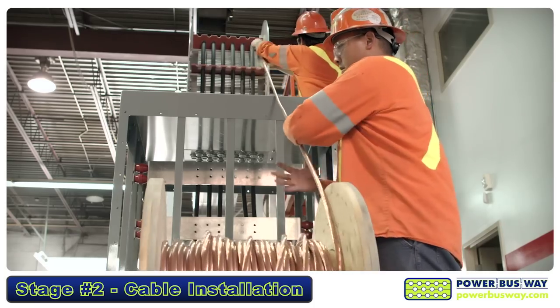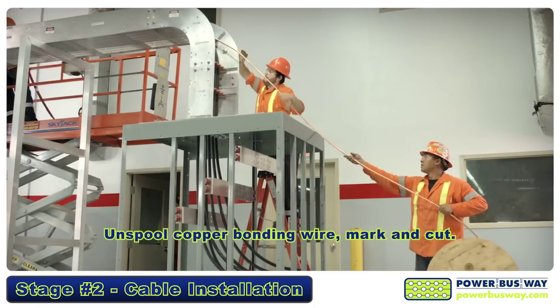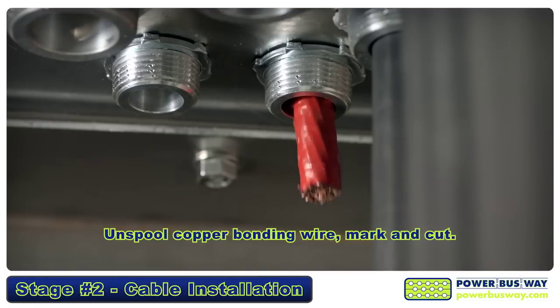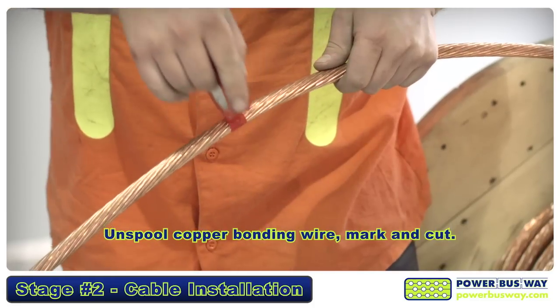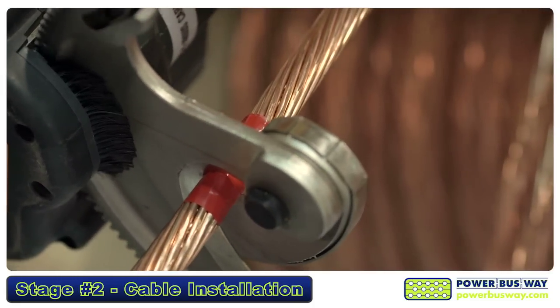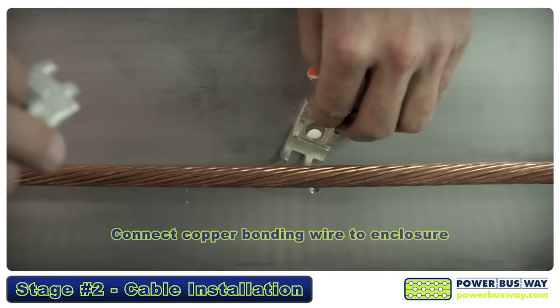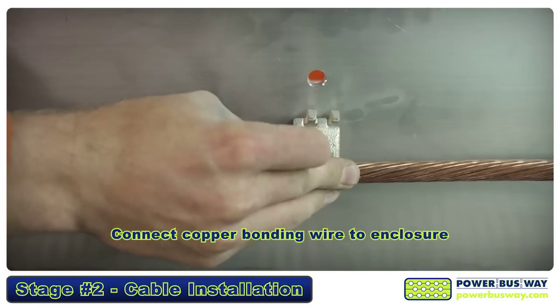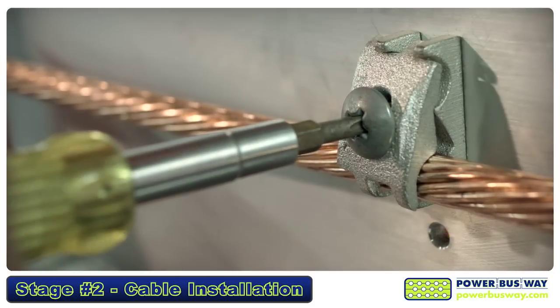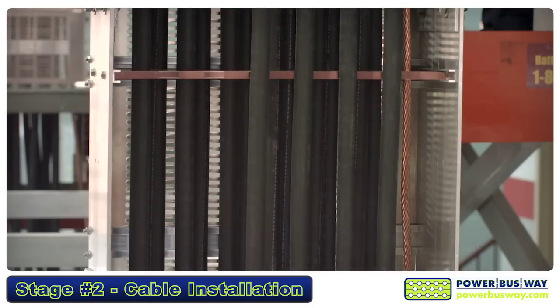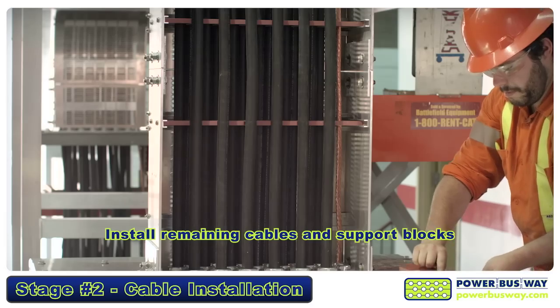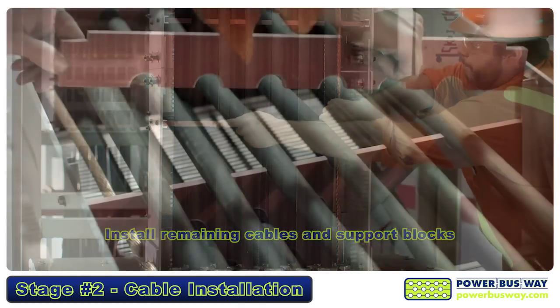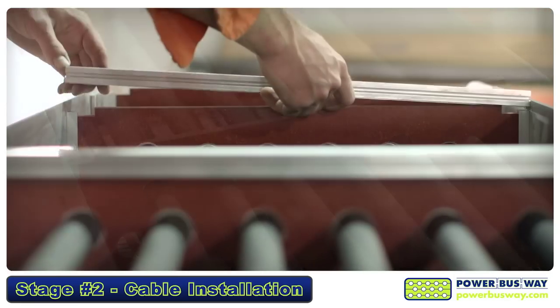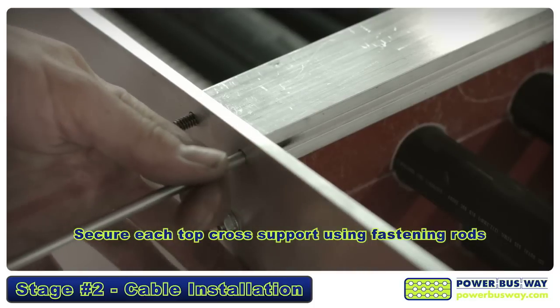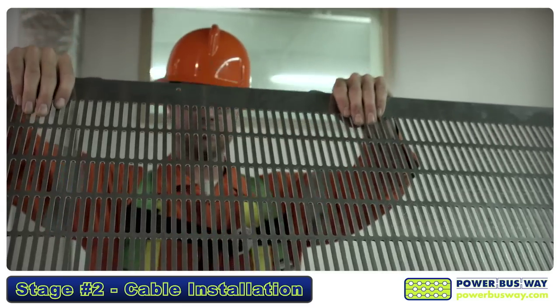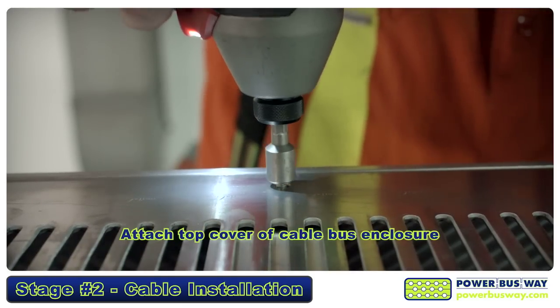Then, unspool the copper bonding wire along the enclosure in the designated locations as shown in the installation instructions. Determine the appropriate length, mark, and then cut. Connect the copper bonding wire to the enclosure using the factory-installed clamps and hardware. Fasten securely at each designated interval. With the bonding wire in place, install the remaining cables into the enclosure, adding in support blocks between layers of cable. Install the top cross support for each cable support block assembly and secure using the fastening rods. Finally, attach the top cover of the cable bus enclosure using the hardware provided.